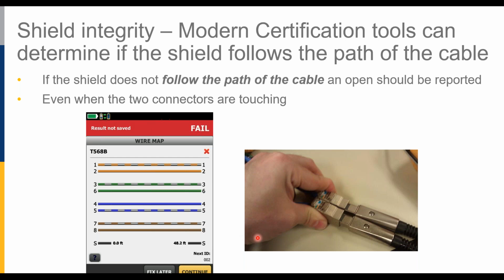We have an interesting trick with ours where we're going to check to make sure that the shield follows the path. Now, if we just did a simple continuity check, you can see that there's continuity between these two shielded connectors. But in the cable tester, it says, wait a minute, the intern who you had terminating this cable tore off the shield and didn't terminate it, so the shield is open on one end. This may also be interesting if your standard is to make sure that the shield is open at one end, given your concerns about ground loops.